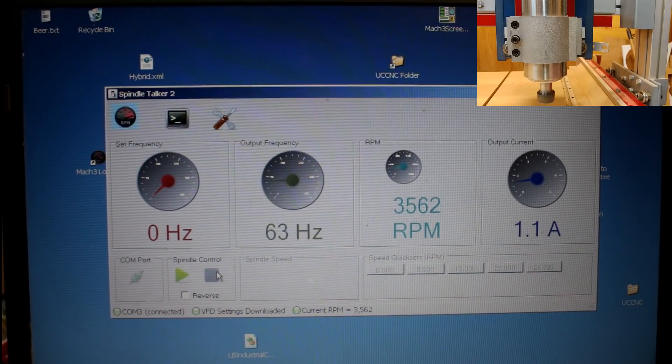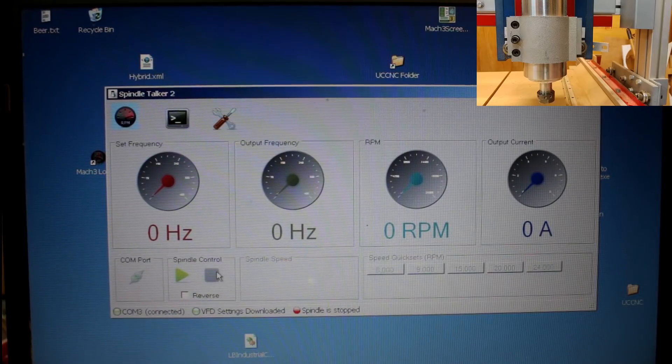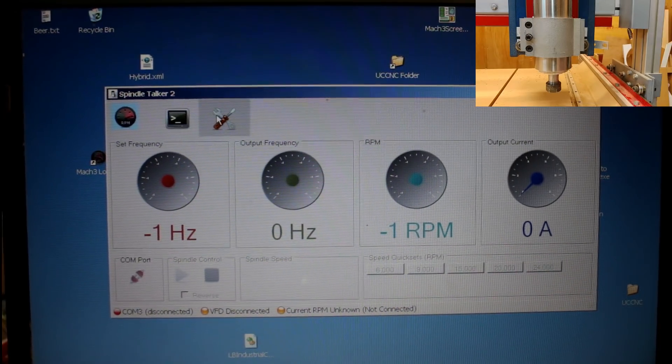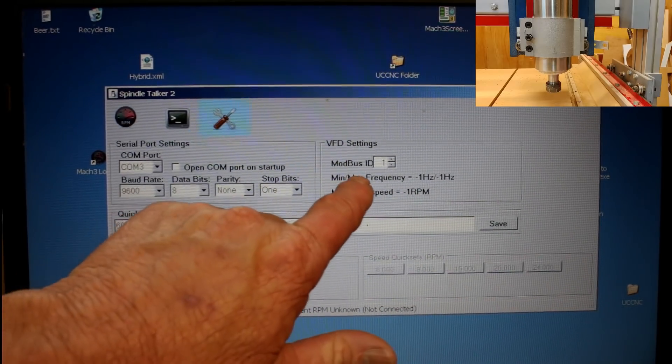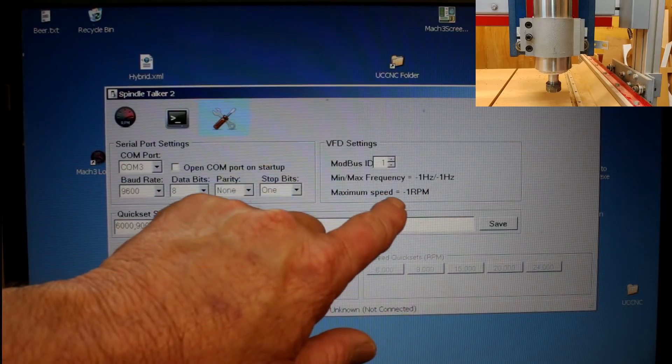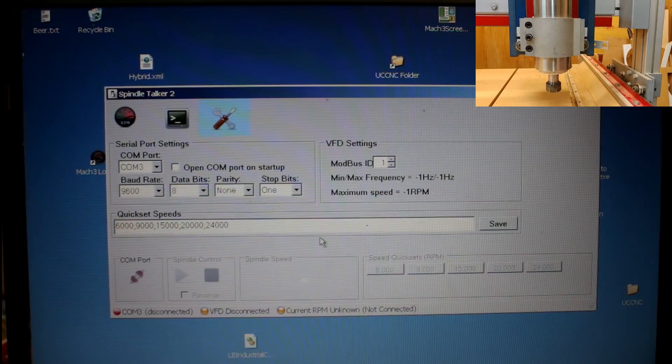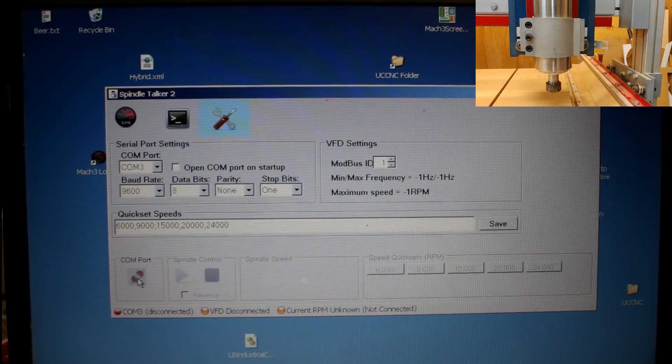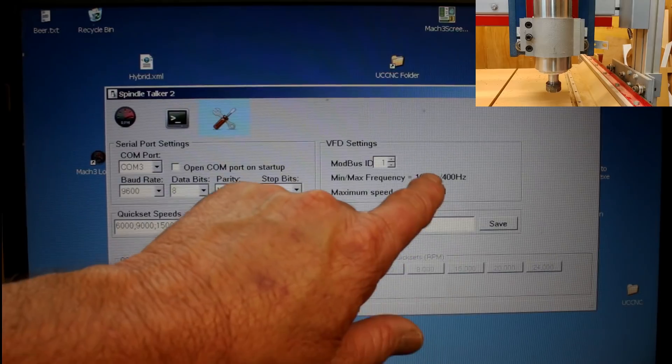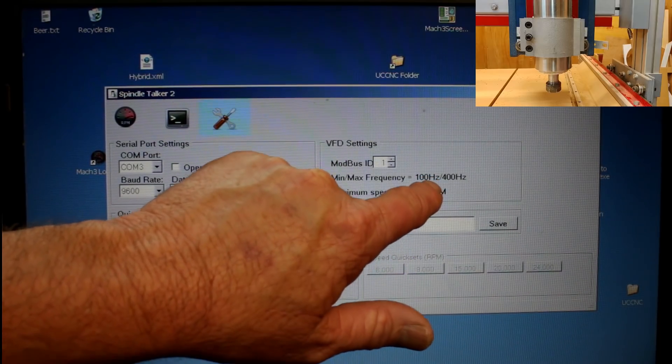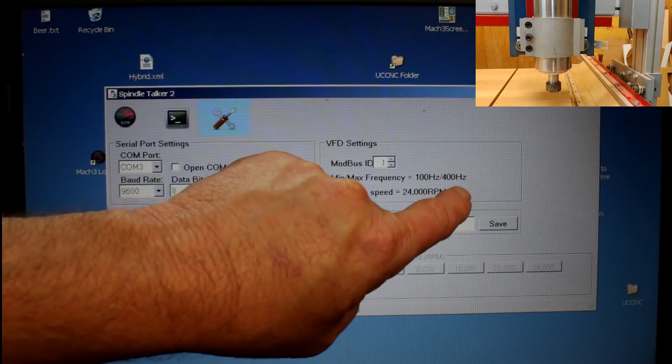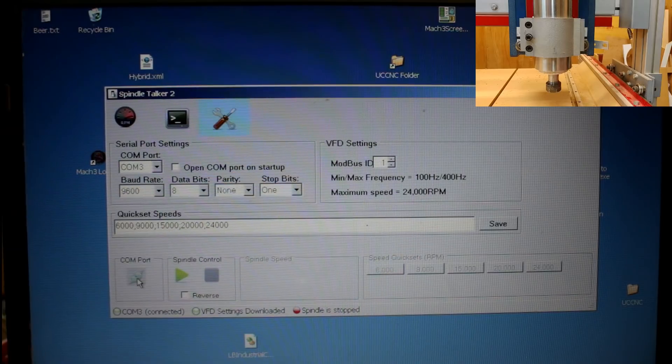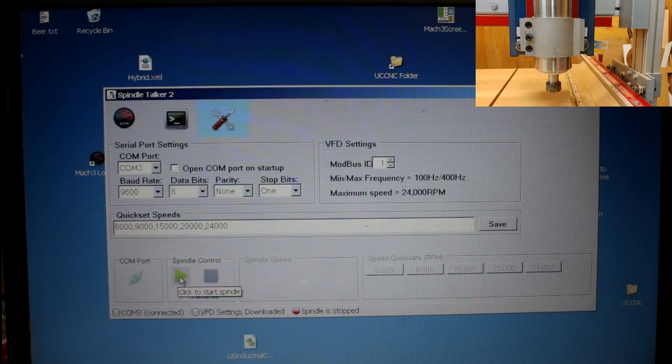So as you can see, my VFD is working fine. Now I'm just going to disconnect the COM port here, and I'm just going to go back into the setup screen. You can see here the information is that there is basically 0 hertz and basically no RPM. But if I actually do a connection here on the COM port, it actually reads the information from the VFD drive, which says I've got a minimum frequency of 100 hertz, so that's 6,000 RPM, a maximum of 400 hertz, and that equates to a maximum speed of 24,000 RPM.